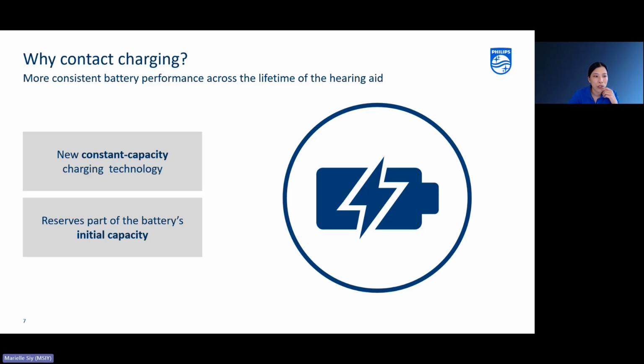That's why we address this, because HearLink 50 uses a new charging technique called constant capacity charging. Here's how it works. A portion of the battery's initial capacity is reserved. Approximately 20% is reserved and not used at all. Then the battery slowly begins drawing on this reserve gradually over time as the capacity naturally degrades. The result is that your client experiences a consistent daily runtime throughout the lifetime of the hearing aid, around 5 years.